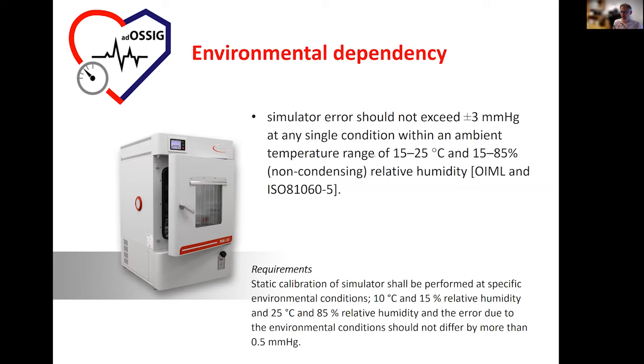So we decided that these conditions should be tested in the most challenging environment, meaning 15 degrees and 15%, and 25 degrees centigrade and 85% relative humidity. So with outer limits, and the differences should not be larger than 0.5 millimeters of mercury.